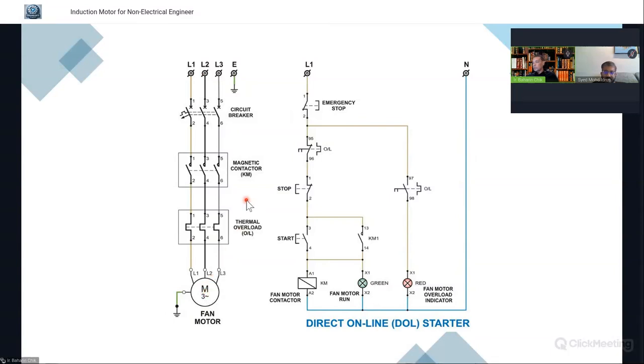Now when we stop the motors, we just press this button, and this is a normally closed circuit. When it opens, it takes out the power to the main contactor, and this opens. So this is a very simple method of starting the motors. When we have issues in terms of thermal overload, this motor is blocked, or the loads are stuck, then the thermal overload will operate. This will open this thermal overload relay, and then the red flag will light up, showing the operators that you need to attend to this motor since there is an overload on this motor.